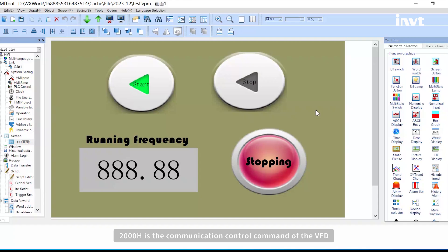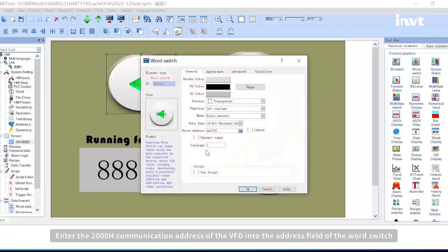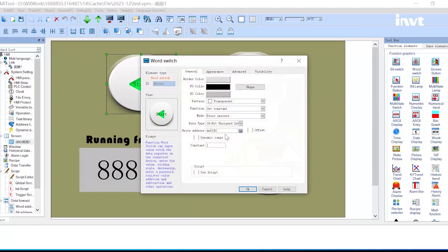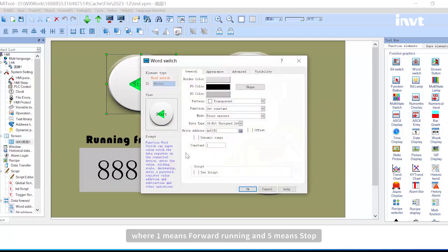2000 hexadecimal is the communication control command of the VFD. Enter the 2000 hexadecimal communication address of the VFD into the address field of the word switch. Set the value corresponding to the control effect and label the name of the button, where 1 means forward running and 5 means stop.